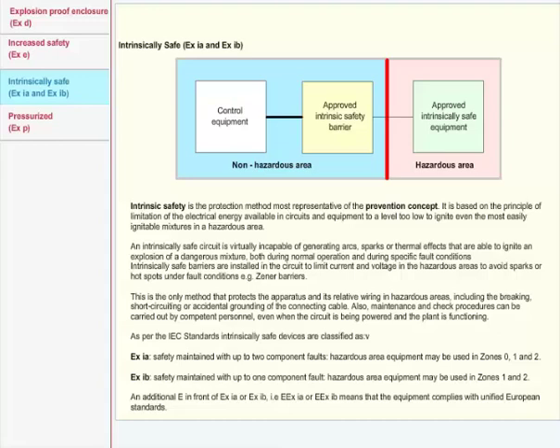Intrinsically safe barriers are installed in the circuit to limit current and voltage in the hazardous areas to avoid sparks or hot spots under fault conditions. Example, Zener barriers. This is the only method that protects the apparatus and its relative wiring in hazardous areas, including the breaking, short-circuiting, or accidental grounding of the connecting cable.